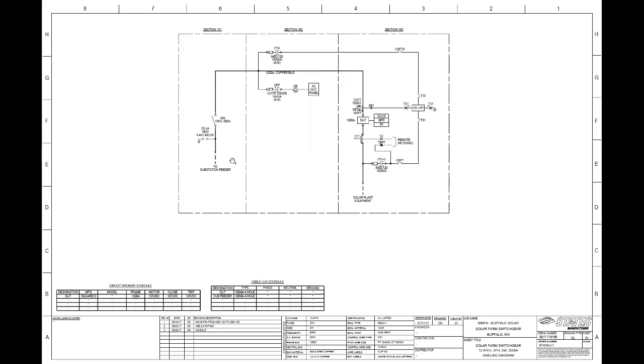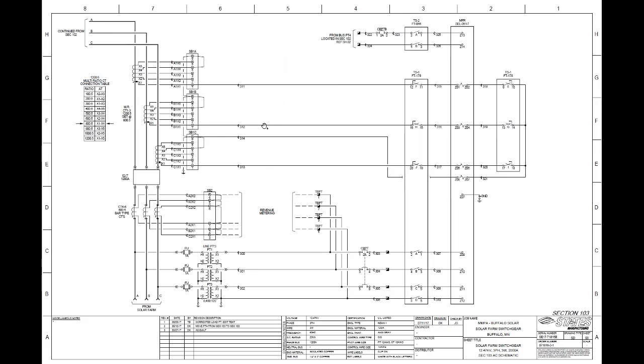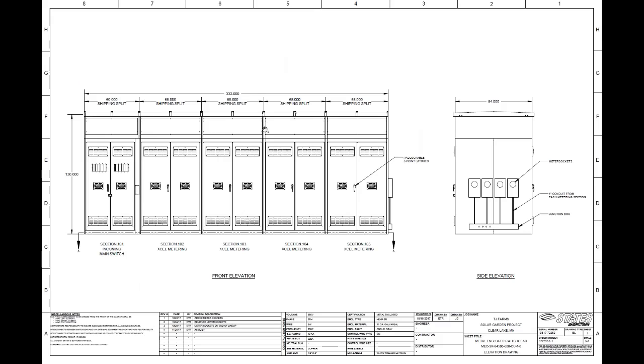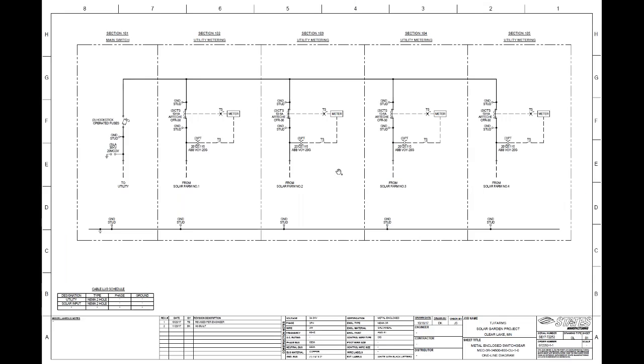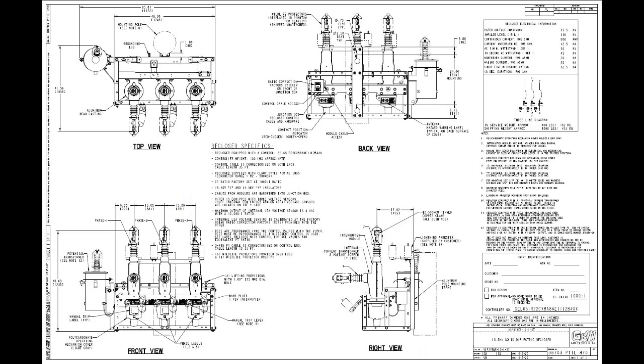Simple one line there. Substation feeder, the solar plant equipment, and the different metering and protective devices on that installation. And this was a solar garden project here in Minnesota that at 35 kV we built different metering bays per the utility's requirements, and then had main disconnect switches for the utility, and the different meters for the utility were located on the end of the equipment. Where you can see just simply different PTs and CTs throughout the different metering bays, and then hook stick operated fuses, and that's the application.